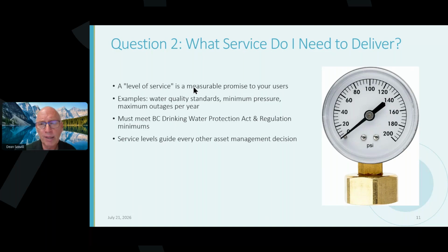So that's a number of 20 psi minimum I've got to maintain. But for customer satisfaction, most people are happy around 30, 35, all the way up to 80 psi, because we don't want to go too high, because then you get great pressure, which can damage service connections.